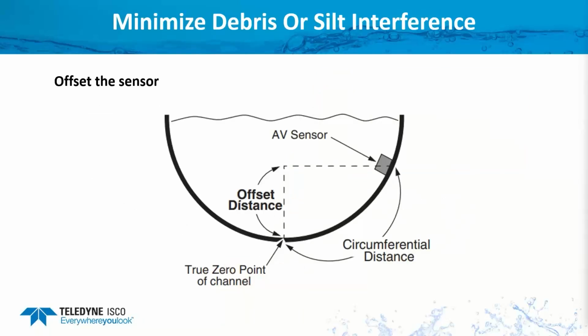Now, other things that you can do: if you find that you have an application where you're constantly going out there to clean it, either because you're going out on a regular basis and you have to clean it, or because you're using the diagnostics and see that it keeps getting covered up with sediment, one thing you can do is offset your sensor. So instead of having it at the bottom where it could get covered with sediment, just rotate it up off the side. This depends on having enough water depth to keep the sensor submerged all the time.